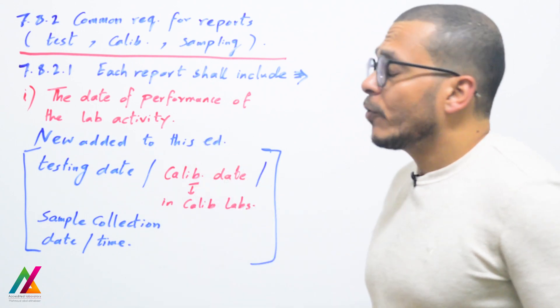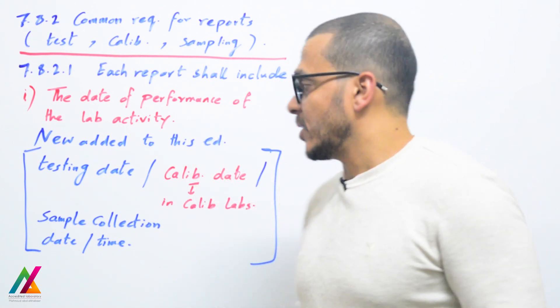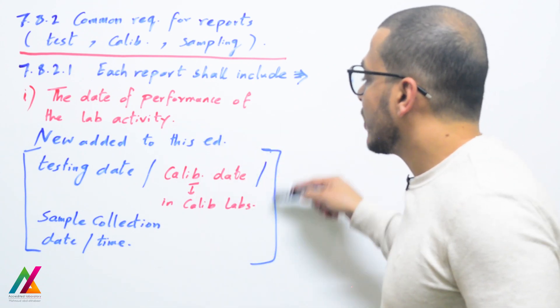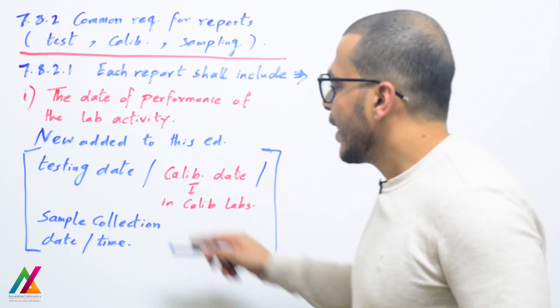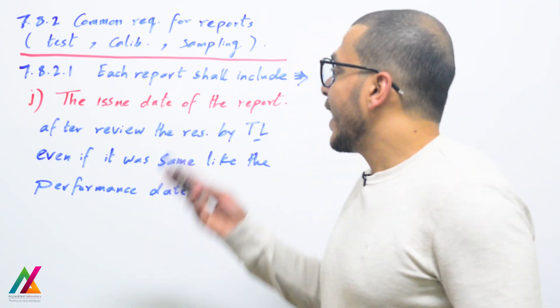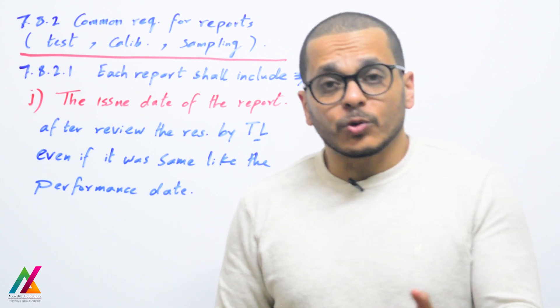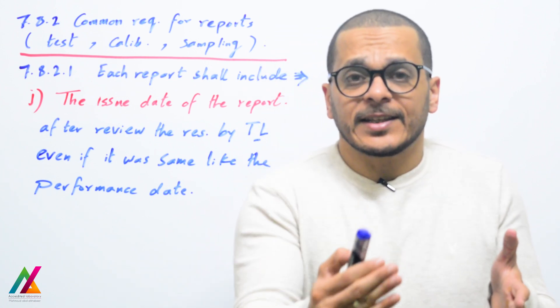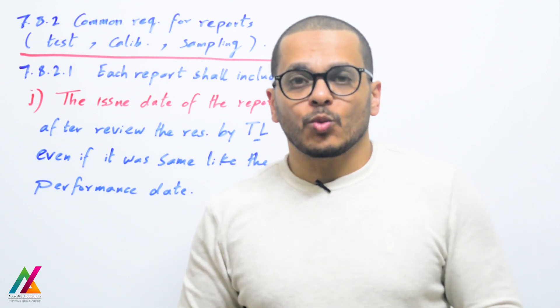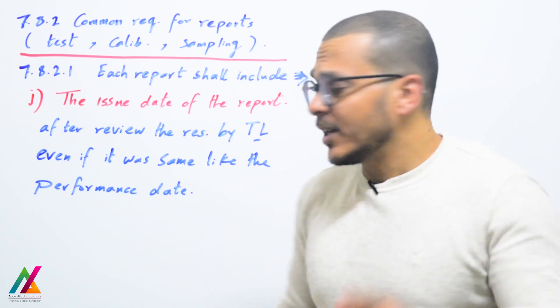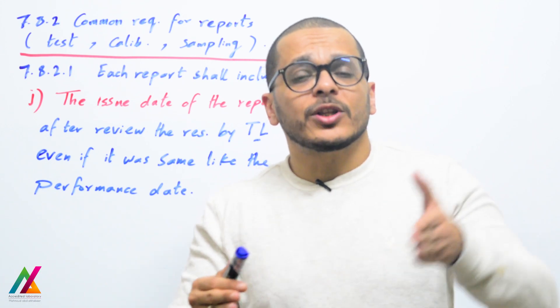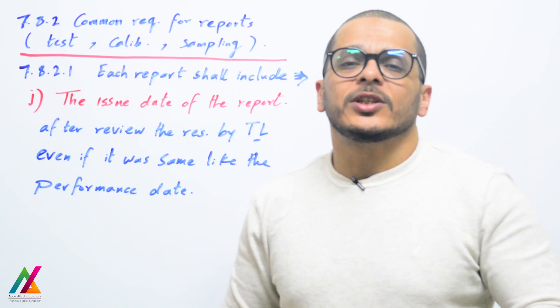The date of performance of the lab activity — when the lab activity was performed — shall also be recorded. This point was added to this edition: the testing date, calibration date for equipment in a calibration laboratory, or sample collection date and time if the lab is responsible for sampling. After that, the issue date of the report — when the report was issued after analyzing the sample and the technical lead reviewed and approved the result — shall be recorded. Even if the performance date and issue date are the same, both shall be recorded in the report.